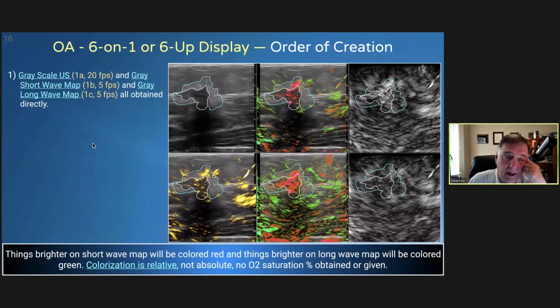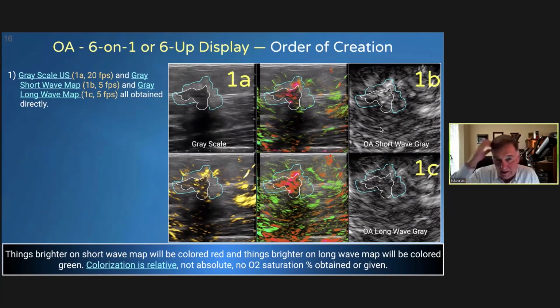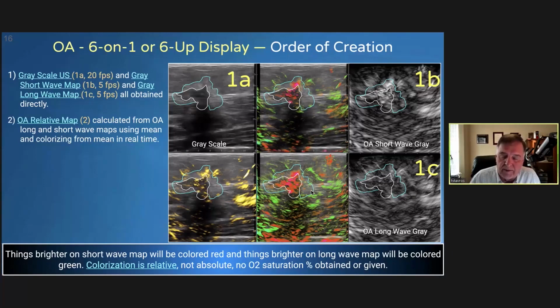So in real time, we're generating the grayscale ultrasound image in the left upper corner and the 2 raw grayscale optoacoustic wavelengths. These are generated as natively acquired frames. Now, the next thing we do is we do a quick mathematical calculation in real time, comparing the long and short wave, and if things are brighter on the short wave, they're colored red, and if they're brighter on the long wave, they're colored green, and we display it in this second map, the OA relative map. That's our most sensitive map.